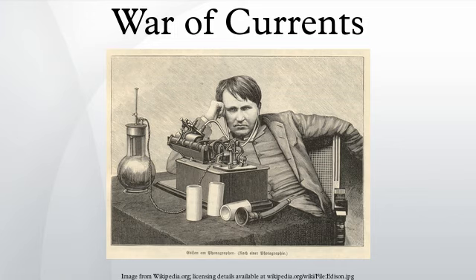Power electronic devices such as the mercury arc valve and thyristor made high-voltage direct current transmission practical by improving the reliability and efficiency of conversion between alternating and direct current, but such technology only became possible on an industrial scale starting in the 1960s. Alternating current transmission lines have losses that do not occur with direct current. Due to the skin effect, a conductor will have a higher resistance to alternating current than to direct current. The effect is measurable and of practical significance for large conductors carrying thousands of amperes. The increased resistance due to the skin effect can be offset by changing the shape of conductors from a solid core to a braid of many small wires.